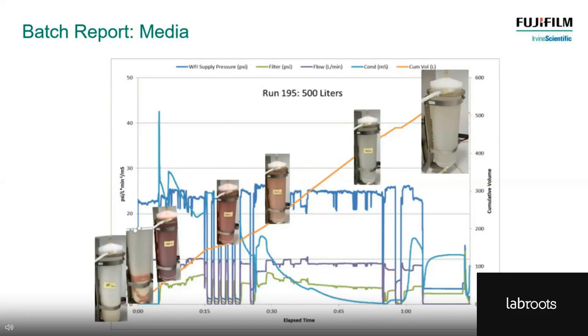As we go through, more and more of the media goes into solution, and the color of that media gets lighter and lighter until everything's in solution and we've got a nice clear media cartridge. Conductivity has dropped down to zero. We then trigger the secondary hydration cartridge, which causes conductivity to spike up again. But we get to a stage where everything's cleared out, everything's in solution, we've made media, and it's been sterilized at the same time. Looking at the elapsed time of this process — it's taken about 1 hour 15 to 1 hour 20 to make 500 liters of media.